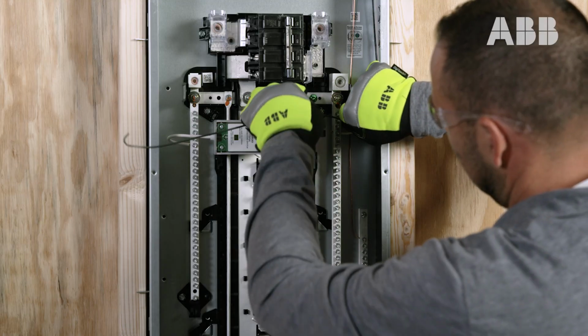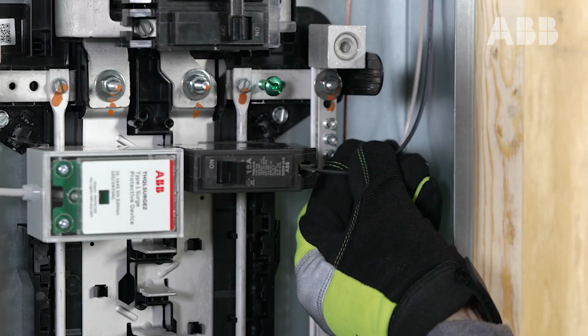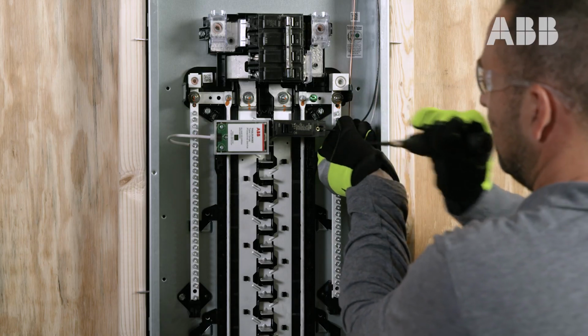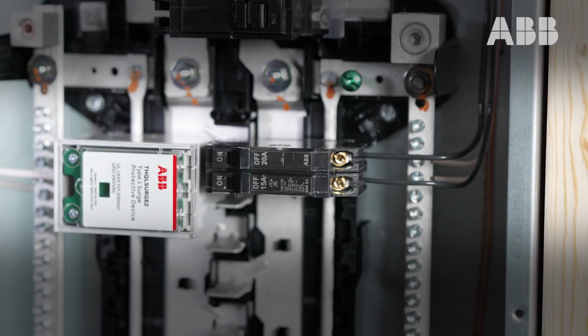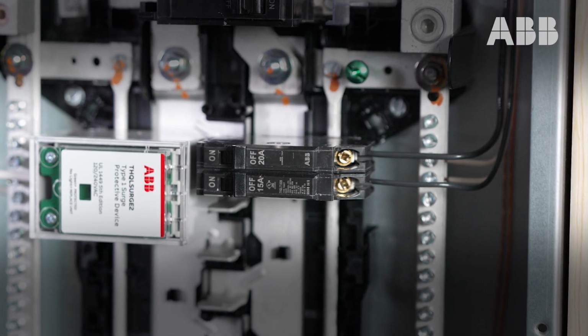Insert the black hot wire into the circuit breaker's lug and torque it to spec. For tandem circuit breakers, repeat this step for each lug.